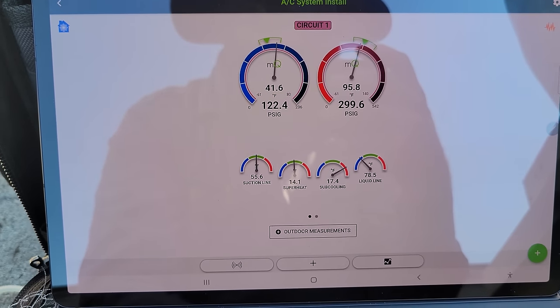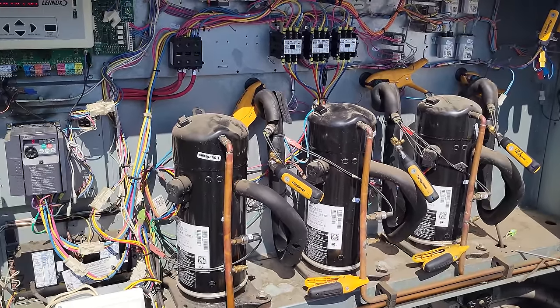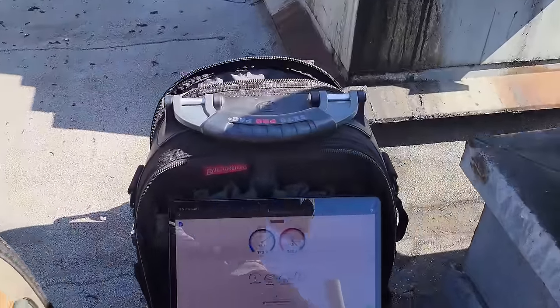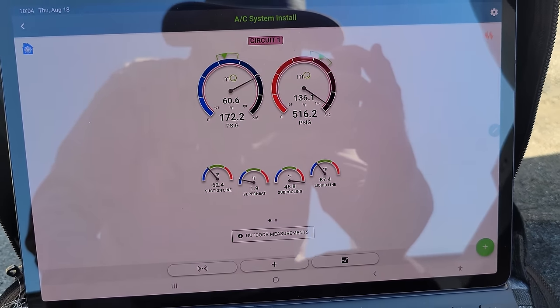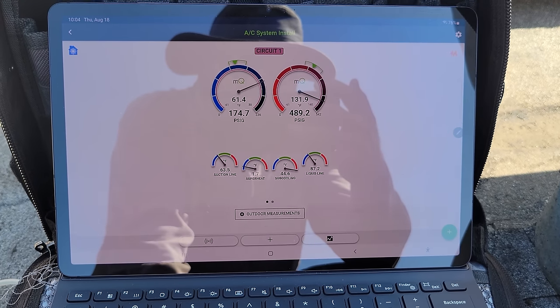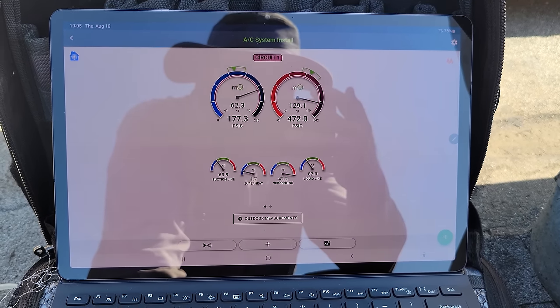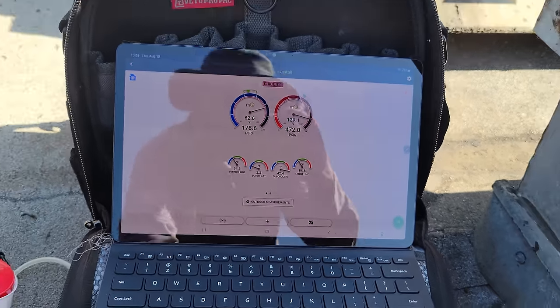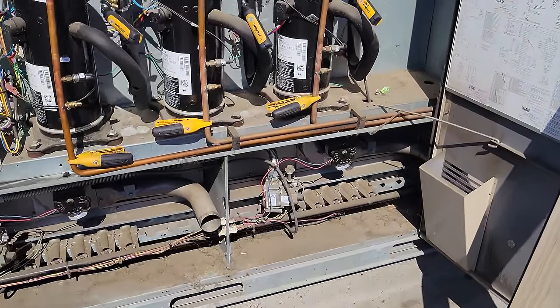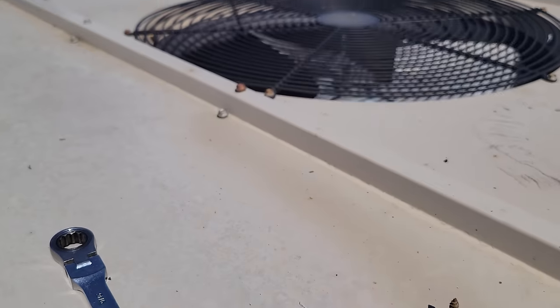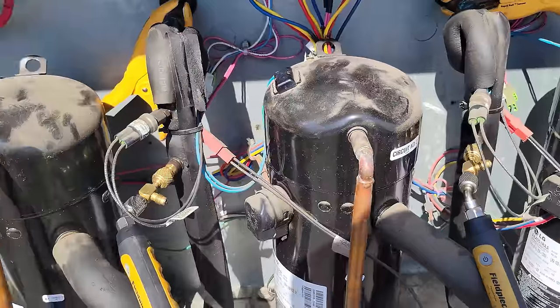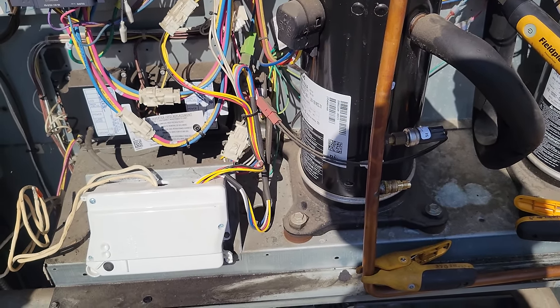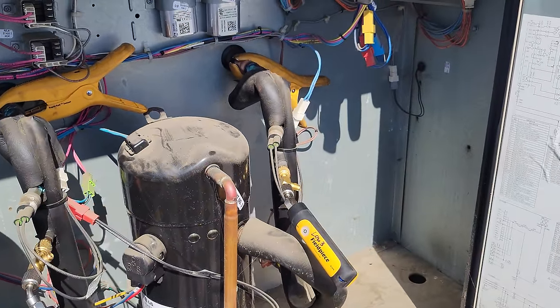I'm going to let it run a few more minutes and get that third stage calling. I had it in test mode and it's weird because it shut off on high pressure again. It shot up way too high on the first stage. Why is it doing that? Condensers are clean, condenser fan motors are running — why would it shut off on high head pressure immediately? What is going on here?